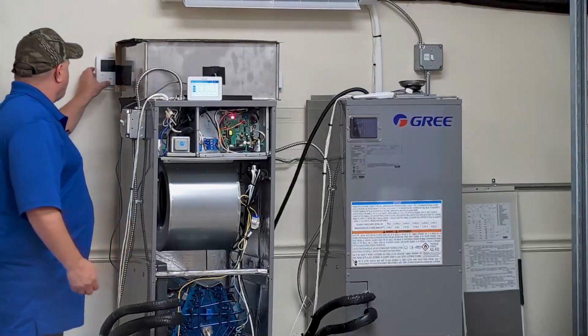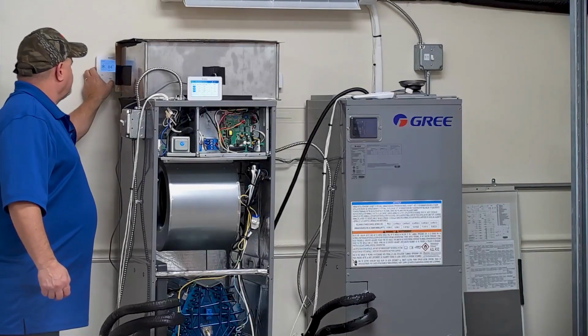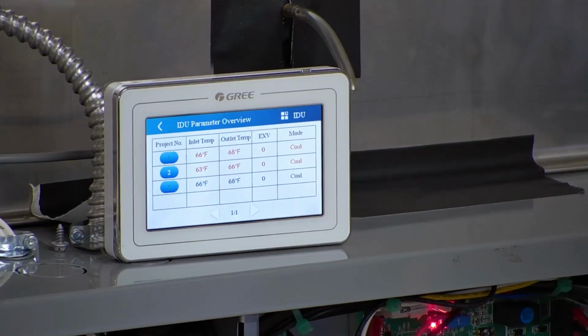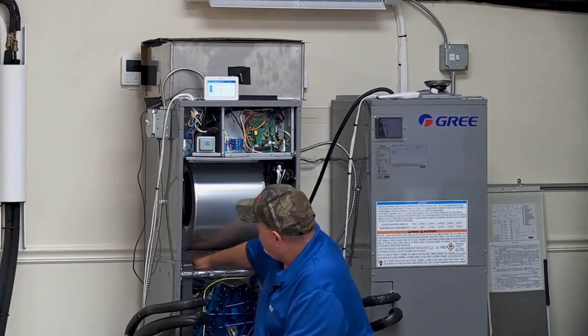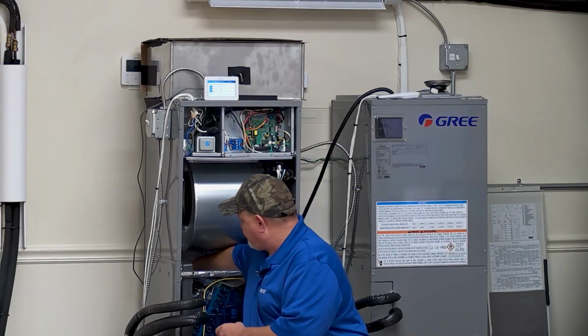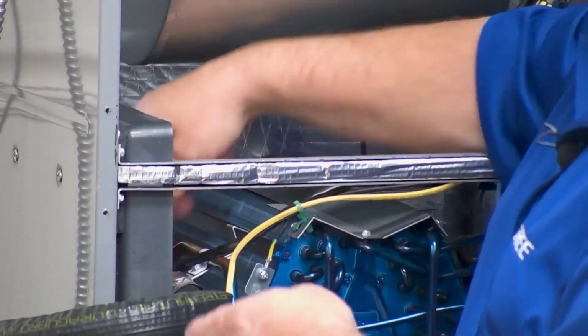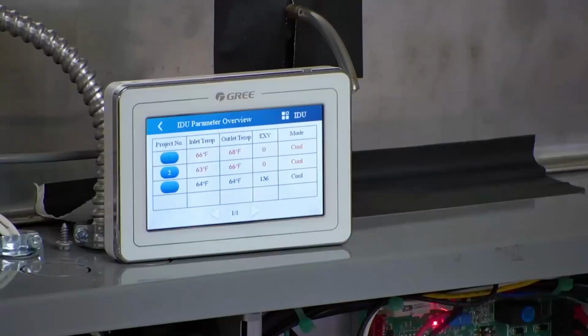Let me give it a call for cooling. Now that I got the unit running, you're going to see the board start giving an EEV call. When it's calling for cooling, there it goes, now it's starting to open the EEV. I'm going to pop the power head off. It's wanting to open it, that's why it keeps jumping that EEV step up. It's not liking the fact that the EEV is not open.